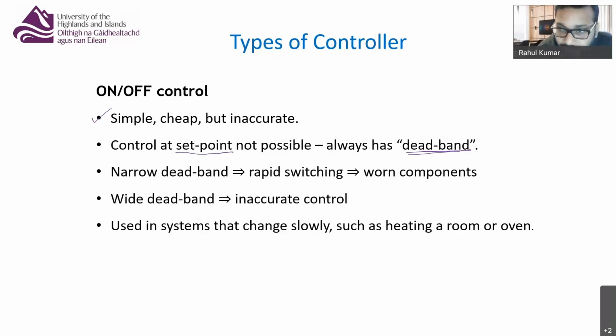Now you can reduce the dead band, right? You can narrow it down. But a narrow dead band will result in rapid switching. Okay, it will increase your switching speed, turning on and off.